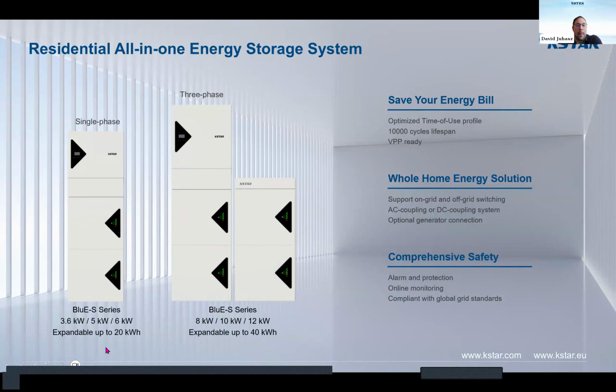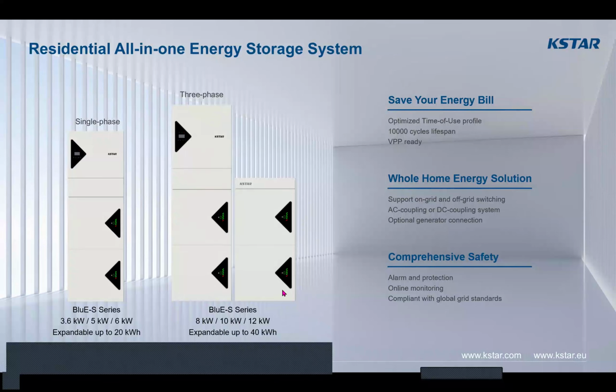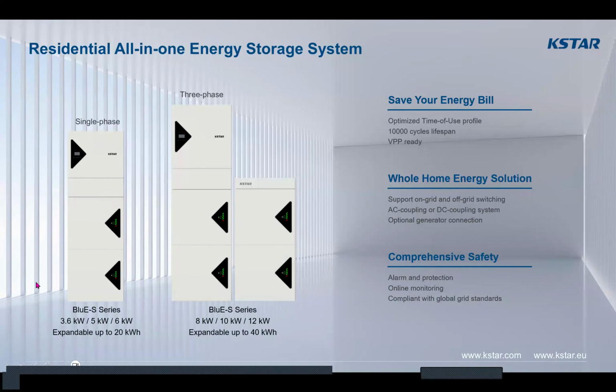Yes. So I have a question regarding expanding the battery capacity. The system that we are using has a 10 kilowatt hour battery pack, and I think the maximum charging and discharging is 0.5 C, if I'm correct. Yes, that's 5 kilowatts. But if we install 20 kilowatt hours or maybe 40 kilowatt hours, is it the same 0.5 C, or is the inverter limited to 5 kilowatts?